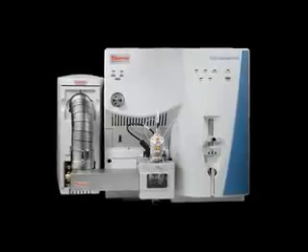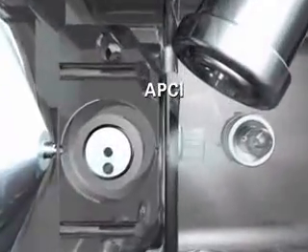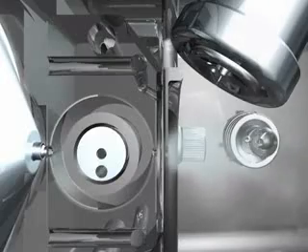The ions are produced in either the heated electrospray source or the atmospheric pressure chemical ionization source. And we use these heated sources because it's very necessary for us to produce dry ions for the FAIMS experiment. These ions enter the annular region between two concentric cylindrical FAIMS electrodes and are transported towards the mass spectrometer entrance via a flow of clean, dry gas. We use a mixture of nitrogen and helium.